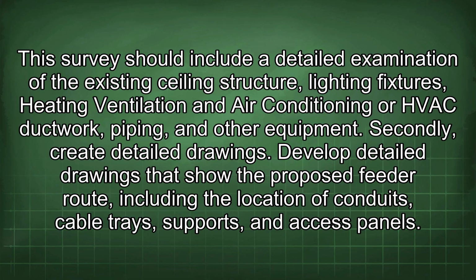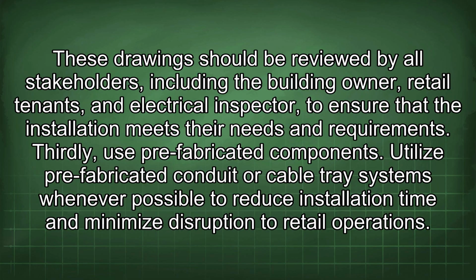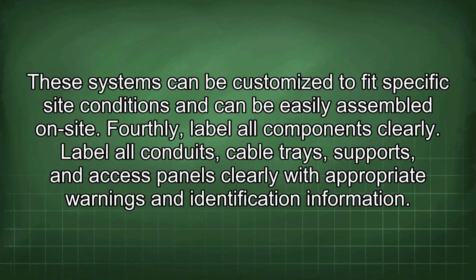Secondly, create detailed drawings. Develop detailed drawings that show the proposed feeder route, including the location of conduits, cable trays, supports, and access panels. These drawings should be reviewed by all stakeholders, including the building owner, retail tenants, and electrical inspector, to ensure that the installation meets their needs and requirements. Thirdly, use prefabricated components. Utilize prefabricated conduit or cable tray systems whenever possible to reduce installation time and minimize disruption to retail operations. These systems can be customized to fit specific site conditions and can be easily assembled on site.